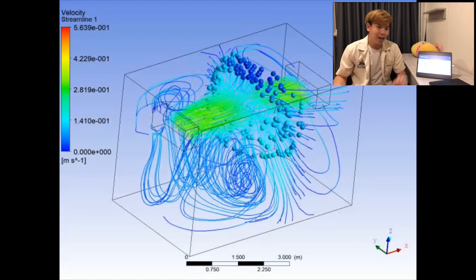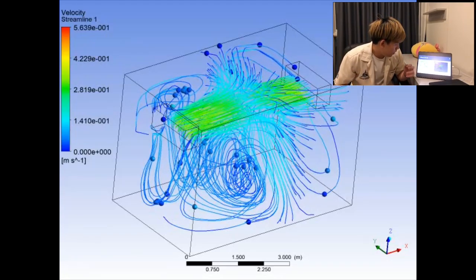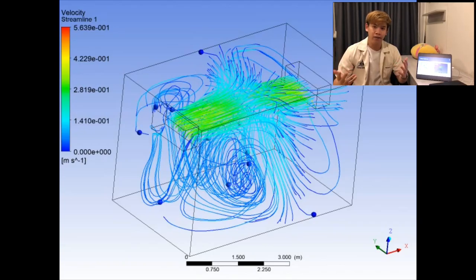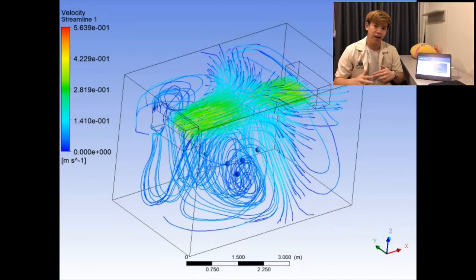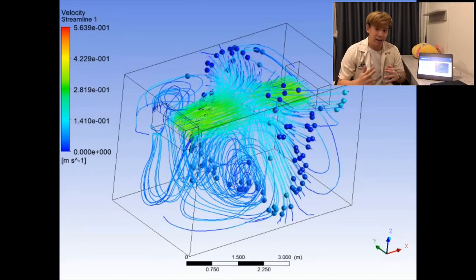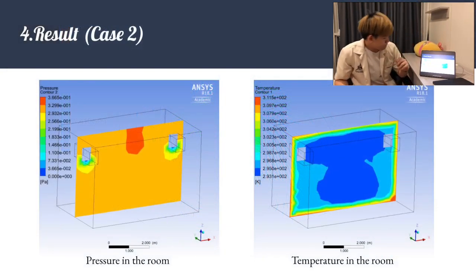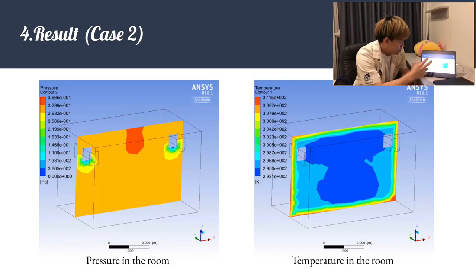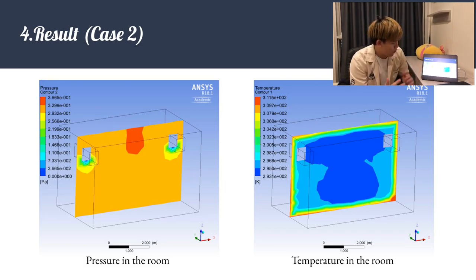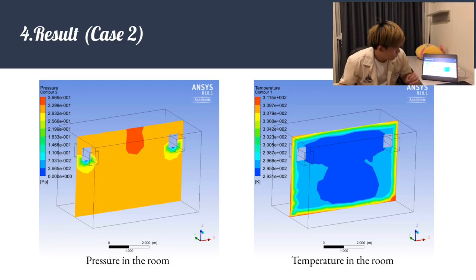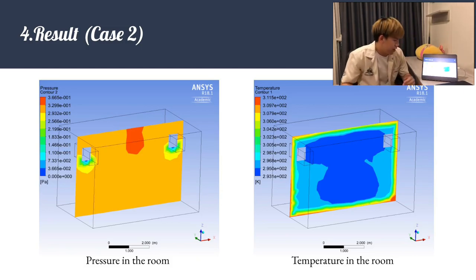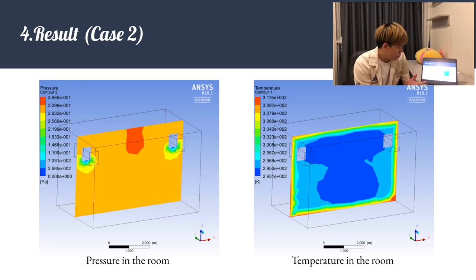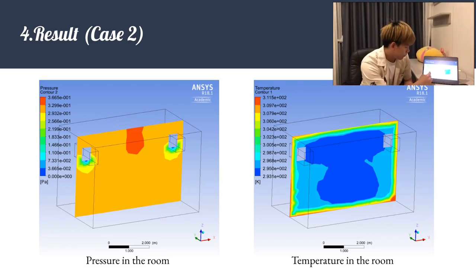For Case 2 with two air conditioners, the streamlines show airflow covering the entire room. The air from both units contacts each other and creates a separated flow in the middle, allowing airflow to spread throughout the whole room. The temperature result shows this is the best solution for cooling the entire room uniformly. The pressure distribution follows the same pattern as Case 1 — high pressure behind the units and low pressure in the middle where streamlines converge.